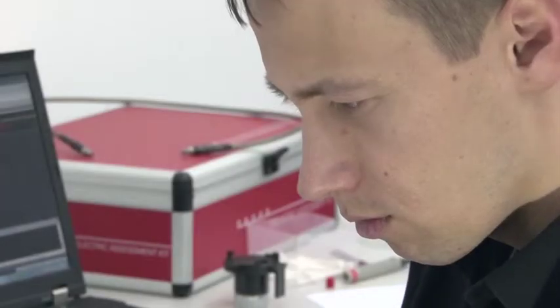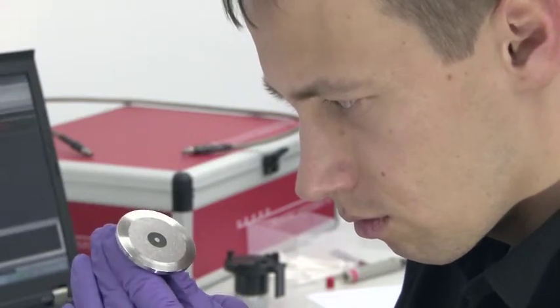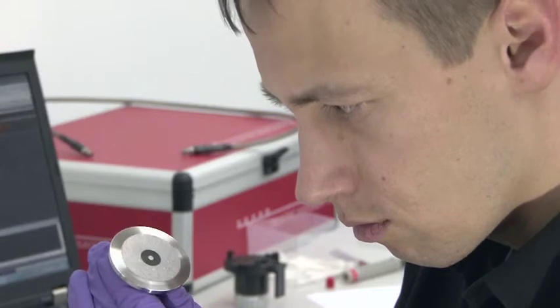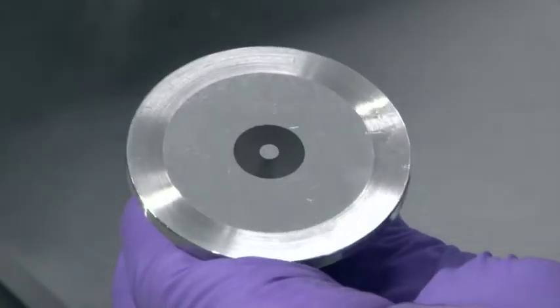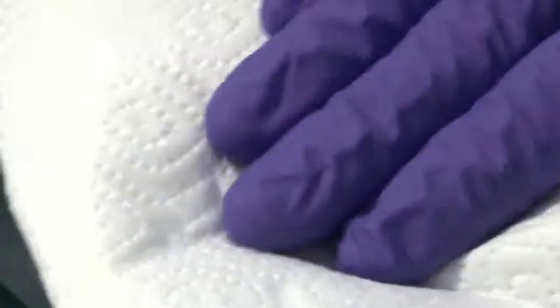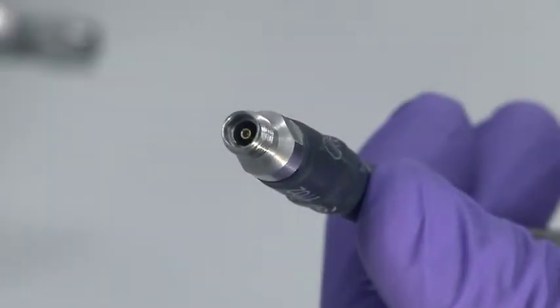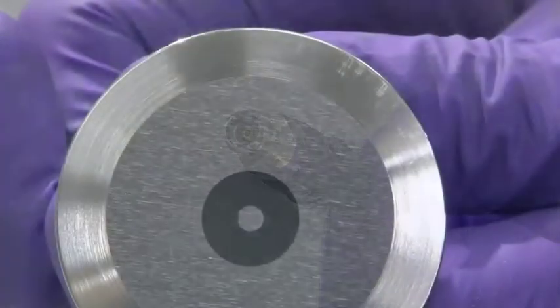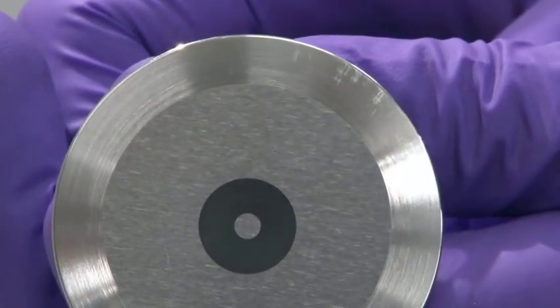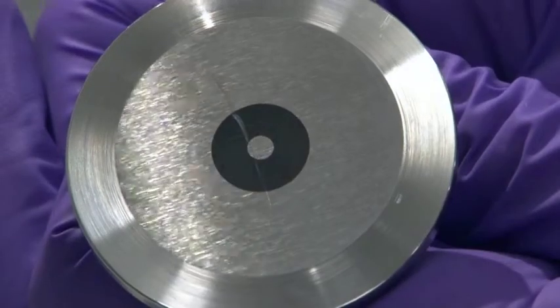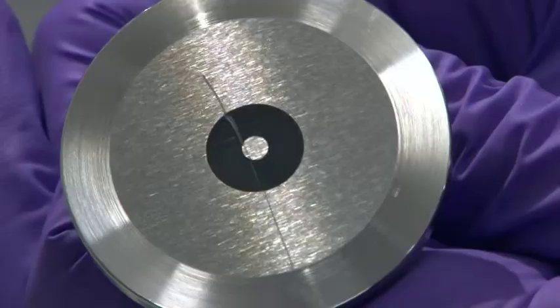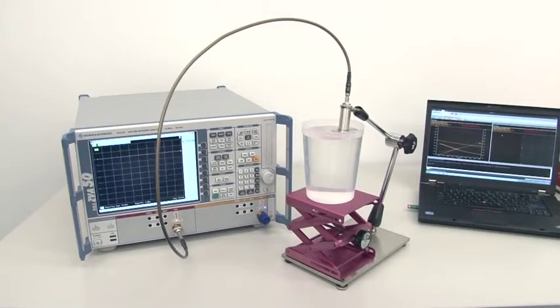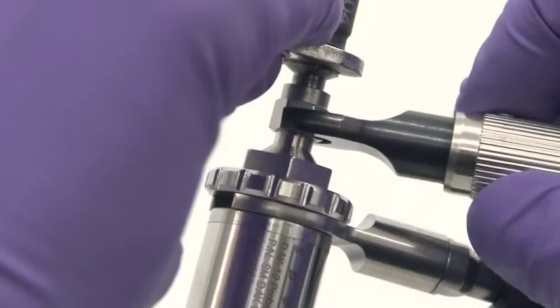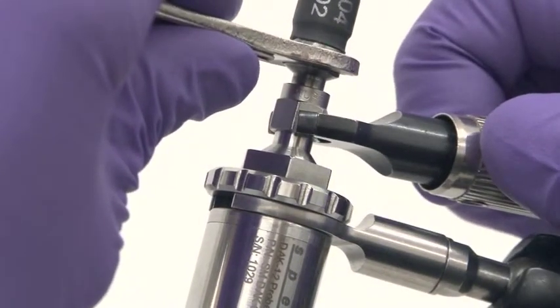The precise measurement starts with careful preparation. Inspect the probe flange and be sure that the surface is clean and undamaged. If necessary, use alcohol for cleaning, like isopropanol. Be sure every coaxial connector is clean in the setup. Small scratches on the flange perimeter do not influence the probe's performance. Scratches crossing the dielectric bead can influence the measurement. In this case, use reference liquids such as methanol or ethanol for the validation. Consult us if you are in doubt. After the inspection, mount the probe and make sure all connections are tight.